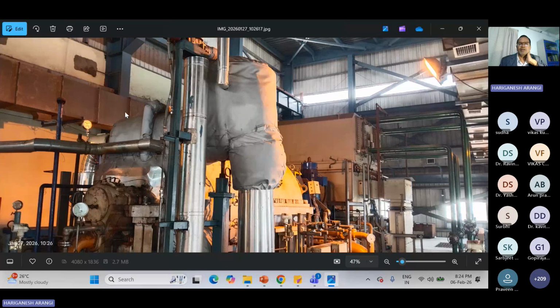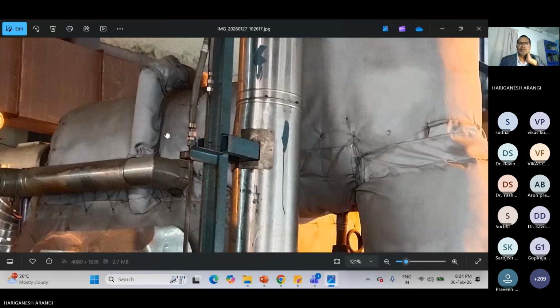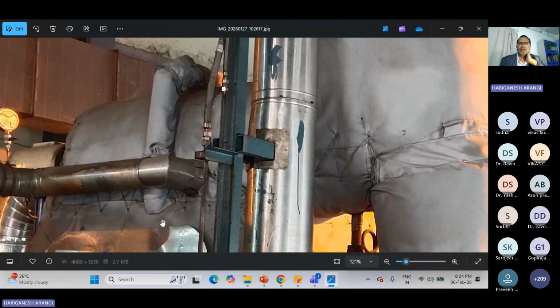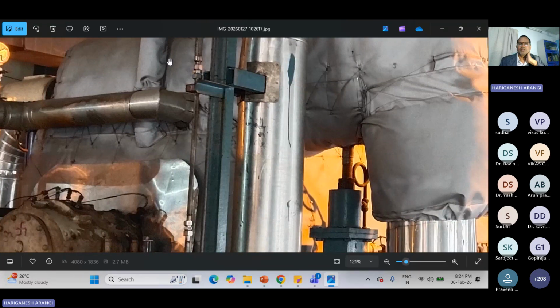Here in this chamber, it is insulated. It will be made with a chromium molybdenum base casing, and because of the temperature of the steam, it should be insulated. Inside the pot, there will be 3 or 4 valves. Those valves operate as we studied in the governor, with respect to the load we are taking. One by one, the valves operate and allow the steam to enter inside this steam turbine.